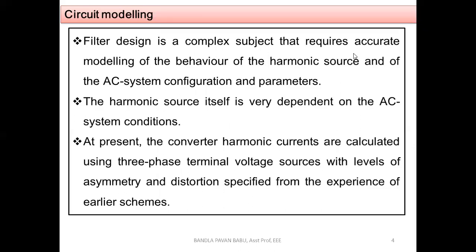The harmonic source itself is very dependent on AC system conditions. If the AC supply feeding the HVDC is operating normally — with constant voltage and frequency — there is no problem. However, if the AC is not proper, harmonic levels increase and harmonic suppression becomes complex, because filters designed to eliminate particular harmonics will be affected if the AC system's voltage and frequency are not constant.